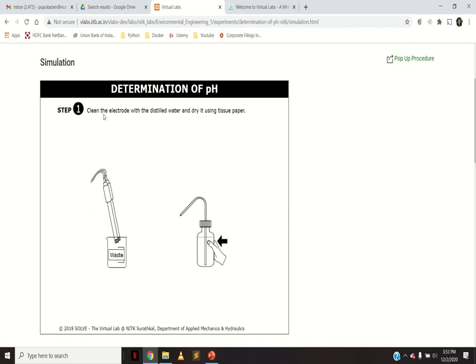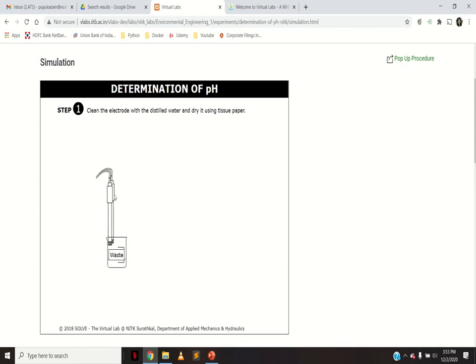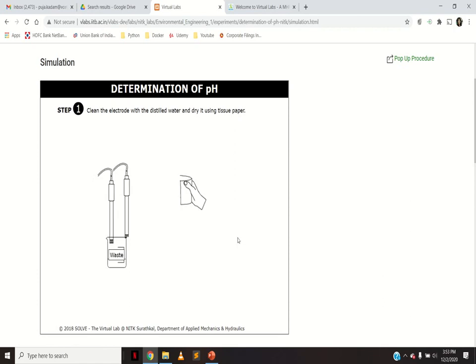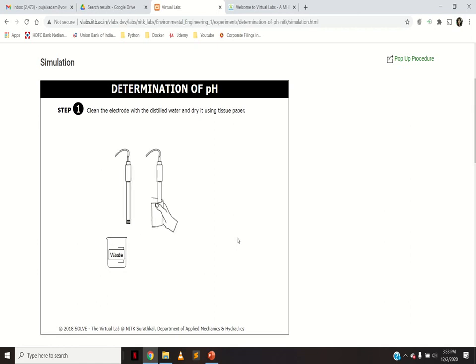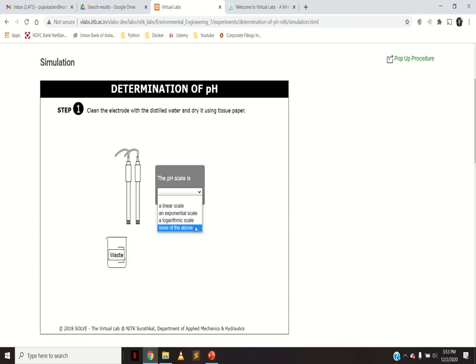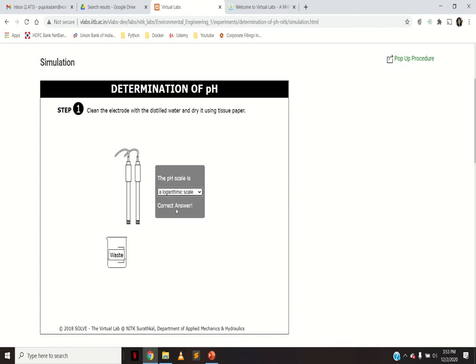For calibration of the pH meter, Step 1 is to clean the electrode with distilled water and dry it using tissue paper. Click and you can see the electrodes are washed with distilled water and dried with tissue paper. There can be one electrode or two electrodes for a pH meter. A question then appears: is the pH scale a linear, exponential, logarithmic, or none of the above scale? It is of course a logarithmic scale, since pH = log base 10 of (1/[H⁺]). The simulation confirms this is the correct answer.